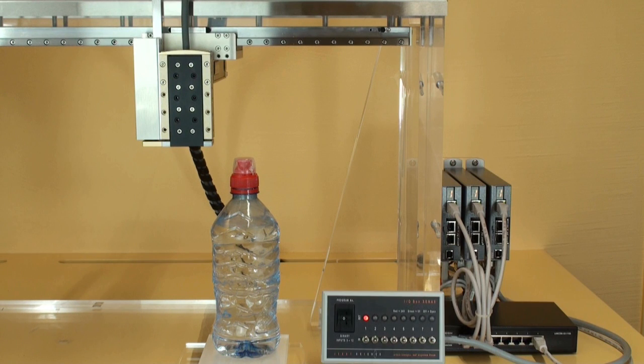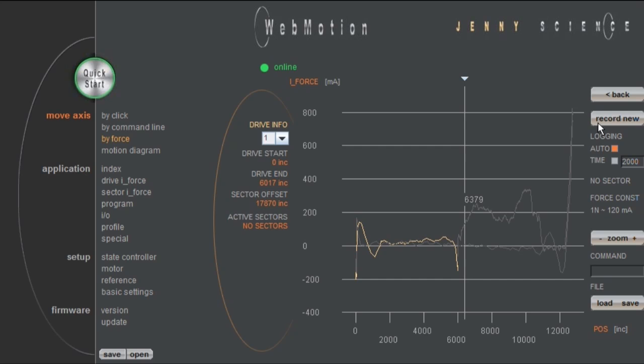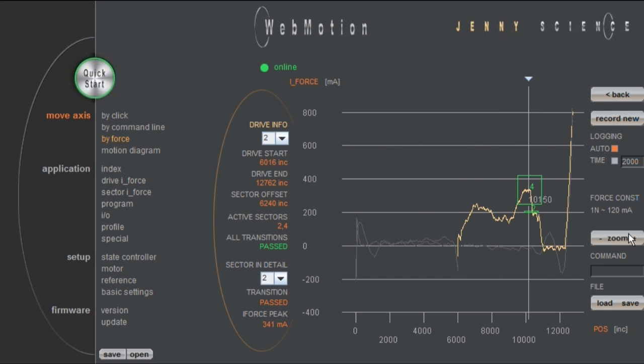In our example we can see that even though the bottle was placed higher, the output still signals that the lid was applied correctly. And having a look at the force-way diagram, the sectors confirm the positive result.